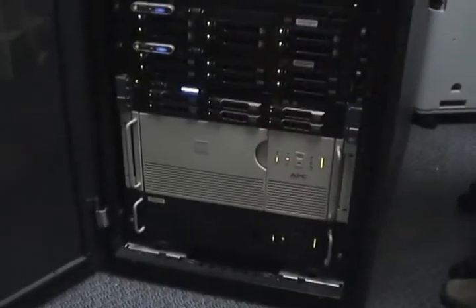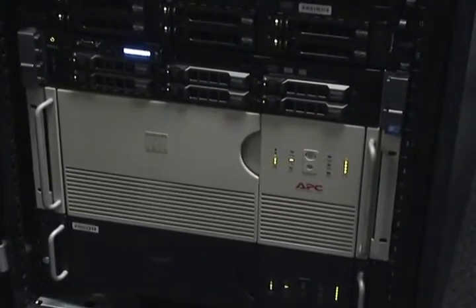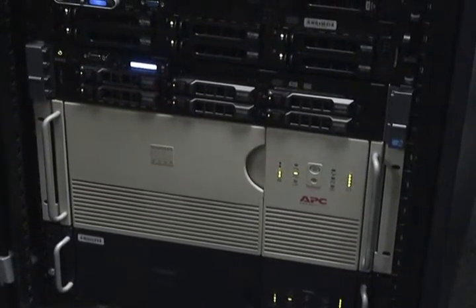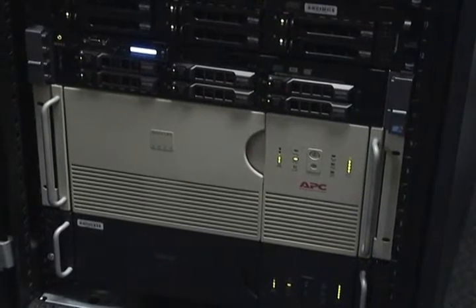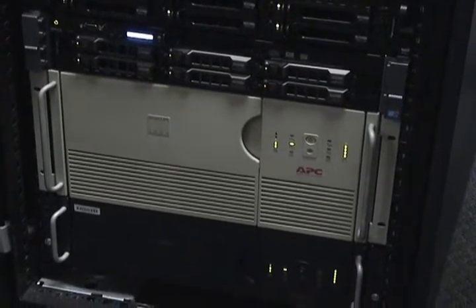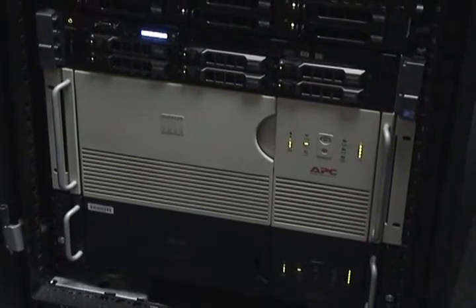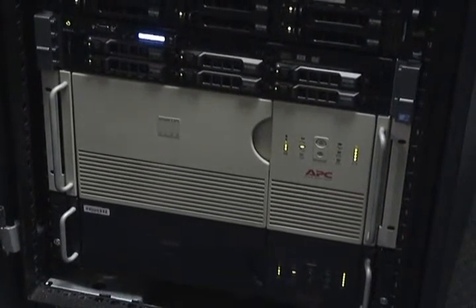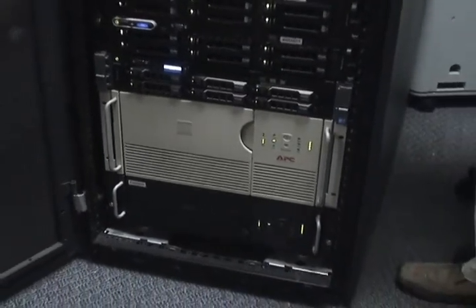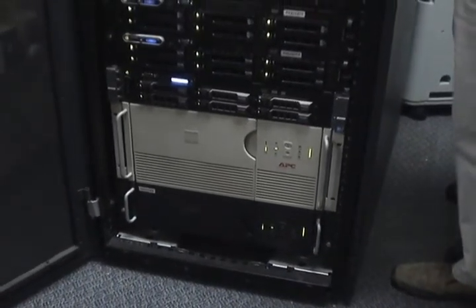So what we have in here, we'll start from the bottom and work our way to the top. First of all, we have two backup power supplies, uninterruptible power supplies. Even though Gravely Hall is a very old building, we got lucky in this sense because there's two electrical conduit lines coming into this room. Those trace all the way back to the hallway where there's two separate circuit boards and underground all the way across the road to where there's literally two separate electrical lines that come in to feed this building. That's because as this place grew, they needed more and more electricity. So eventually Idaho Power said, okay, we've got to run a whole new line. When we discovered that, I said I want one line coming in from one of those main lines and another one coming in from the other.